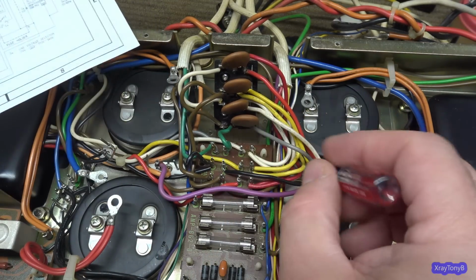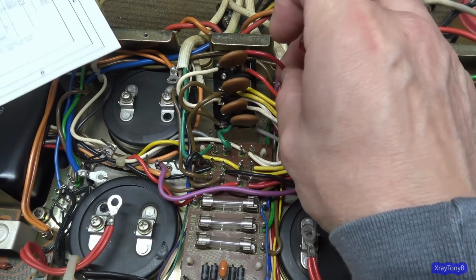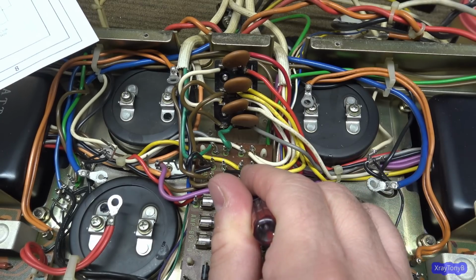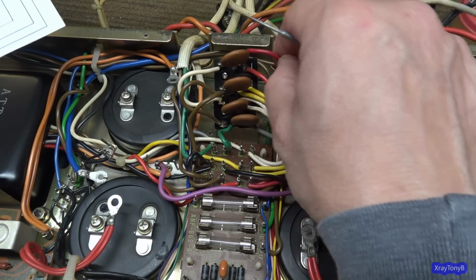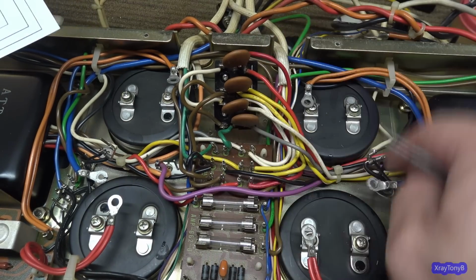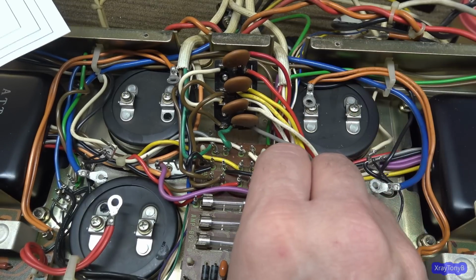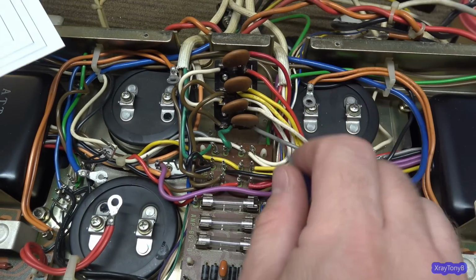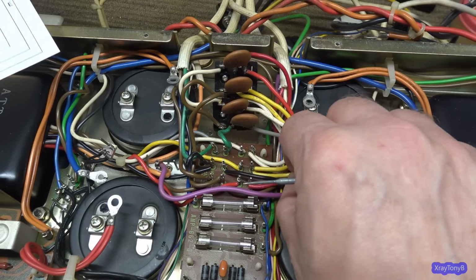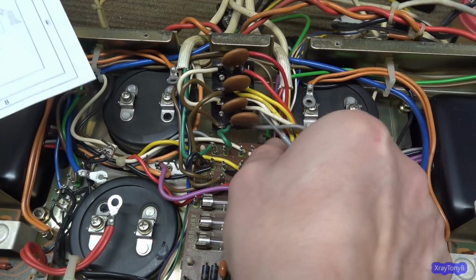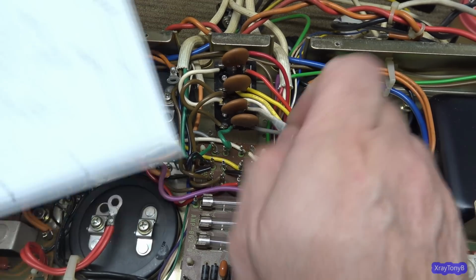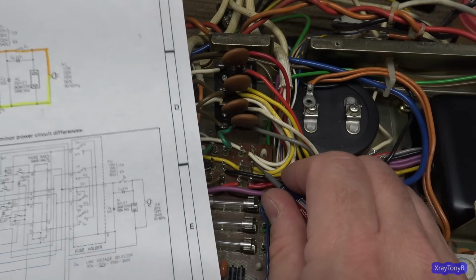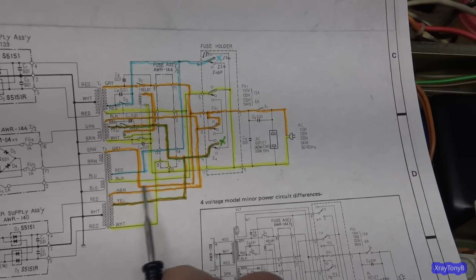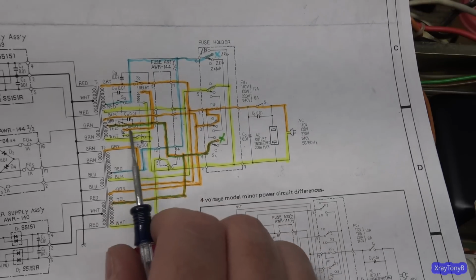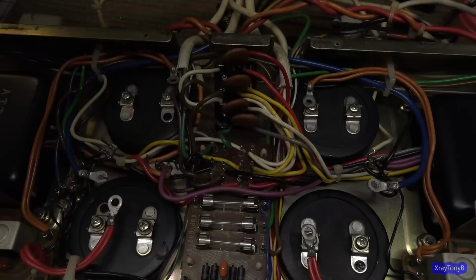One of them is just a jumper going over to here, and I'm going to remove that jumper. Then I'll take this wire that's coming from the transformer and connect it over to here, so that gets rid of this. Then I'll do the same thing with the yellow - remove the yellow jumper, which is this one right here, take this yellow wire off, and connect it to here. So that's essentially all I'm doing, is just bypassing these relay contacts.